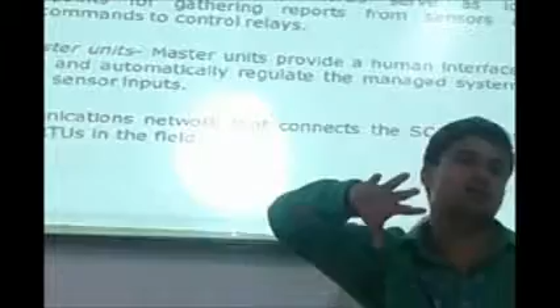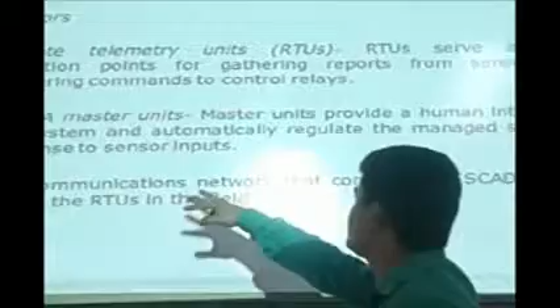Next one is the communications network that connects the SCADA master unit to the RTUs. The same thing, those networks are LAN, Ethernet and WAN. These are all the communication networks that connect the SCADA master unit to the RTUs in the field.